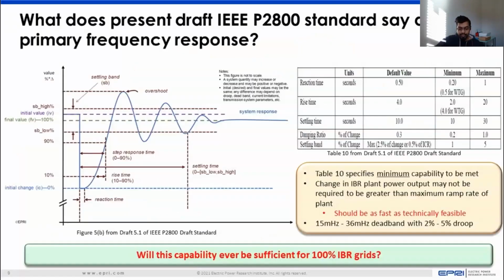Presently, there is in IEEE a draft standard being formulated, termed 2800. This draft standard builds upon, or takes lessons learned from, IEEE 1547, which was for distribution-connected inverter-based resources. Using that as a starting point, it has been drafted to cater to bulk power system connected inverter-based resources.